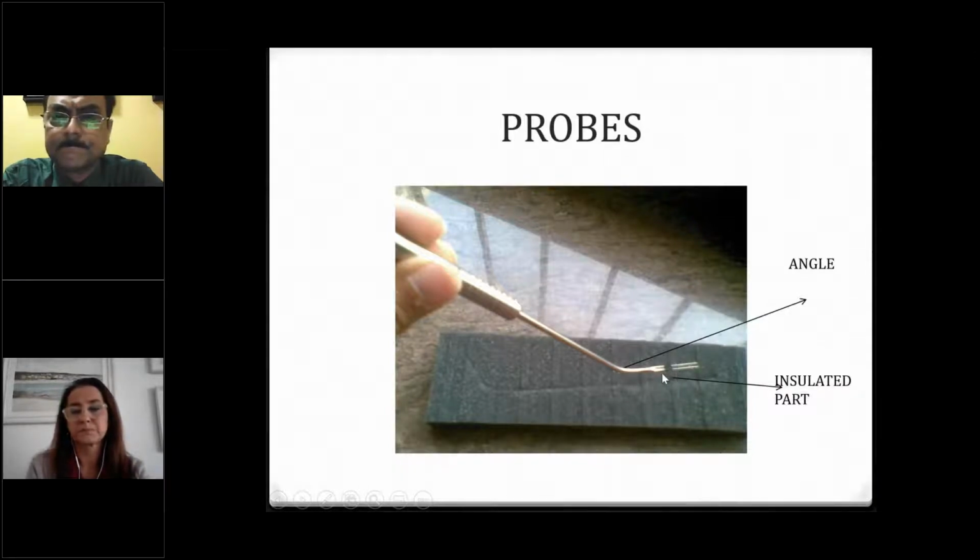This blackened portion is the intermediate portion which acts as an insulator, so that no radiofrequency current from the non-insulated part passes on to the instrument, nor does it pass on to the tissue or the organ structures of the patient out here. So it is one of the safety mechanisms of radiofrequency.